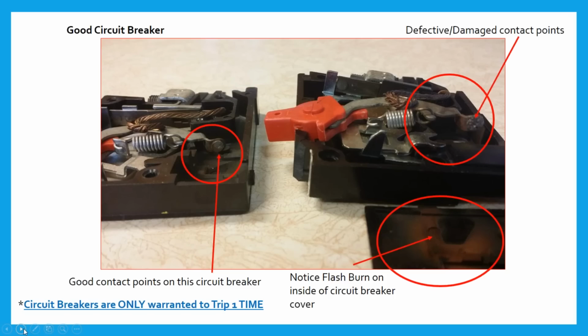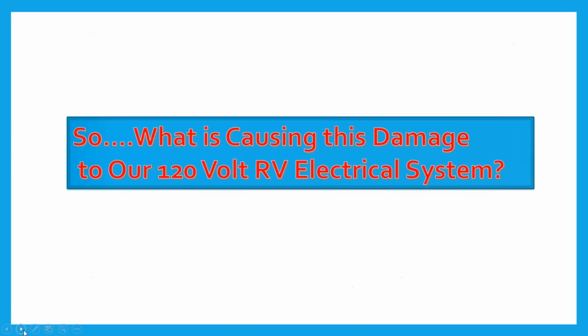I want you to notice as well, when I peeled open this circuit breaker, look at how it flash-burned on the inside of the cover. This flash burn shows us something was taking place, there was heat, but also that thing had to be arcing in there. When you start to see this happening, you just say, okay, this thing is a disaster waiting to happen. It looked just like that motorhome, or just like those circuit breaker panel boxes we were just looking at a few moments ago.